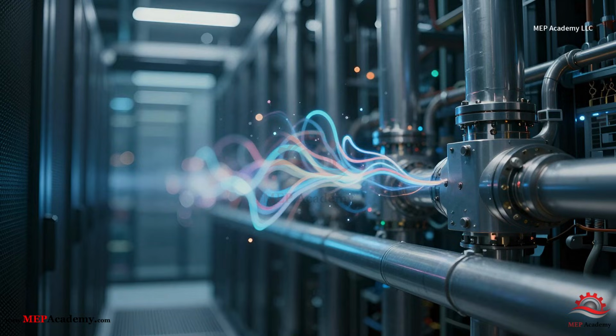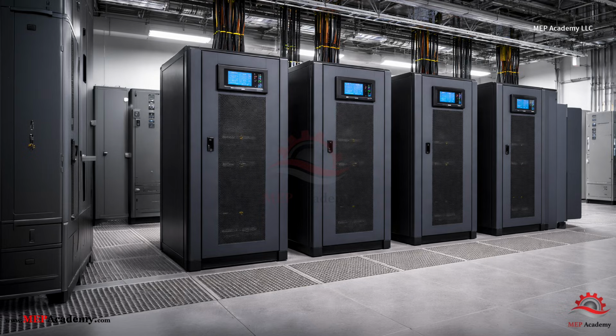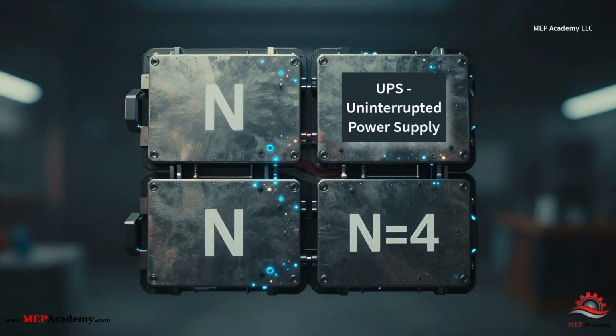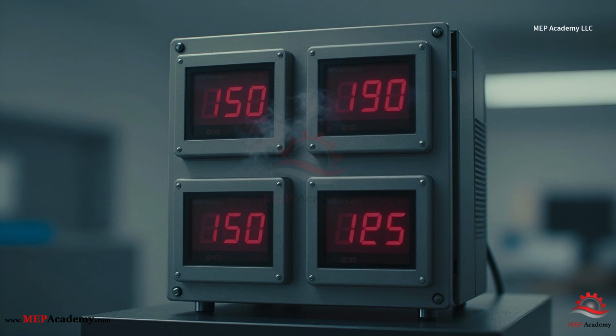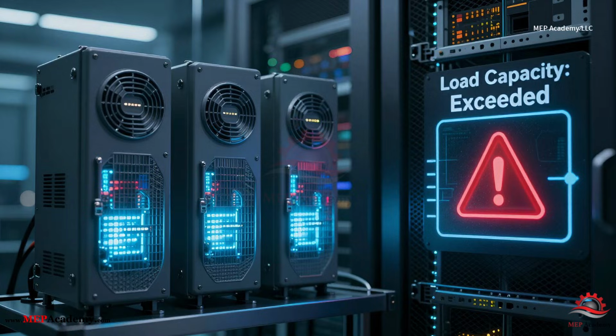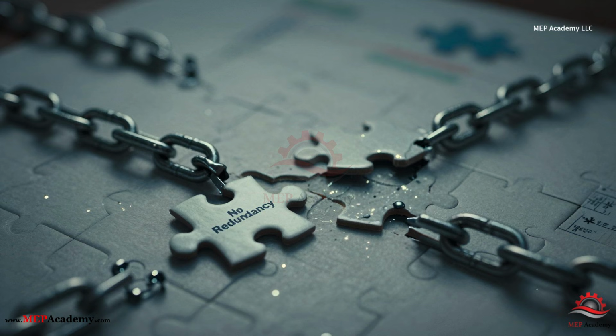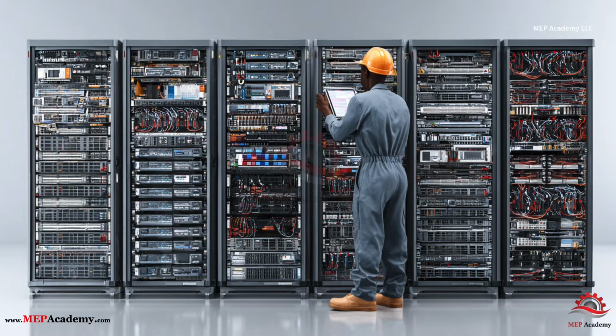The same concept applies to electrical systems. Imagine a data center requires 4 UPS modules to provide enough electrical capacity for the IT load. Those 4 UPS units represent N capacity. If one UPS fails, the remaining units may not be able to support the entire load. This configuration has no redundancy, and most modern data centers avoid operating this way.